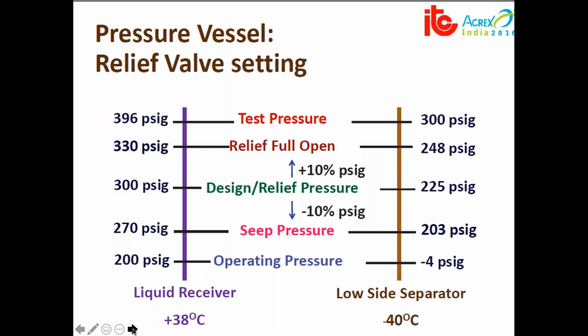Operating pressure is 200. 300 is the design pressure of the pressure vessel. 330 is the relief pressure, with the safety valve fully open. And your test pressure is 396. This is for the high side. Similarly, I have indicated the set pressures for the low side at minus 40. You can calculate for minus 20 according to the same chart. This chart will be available to all of you.